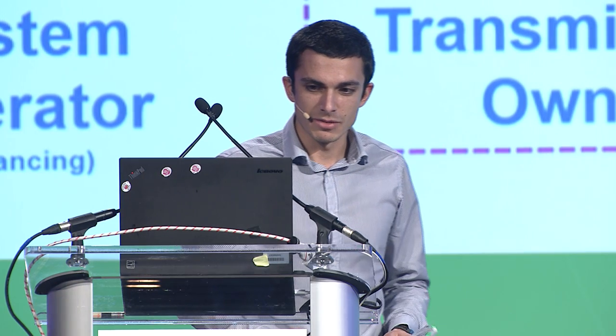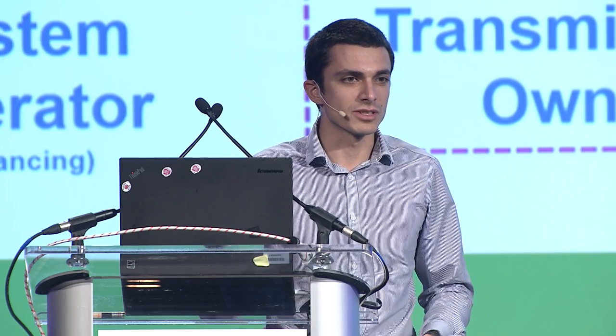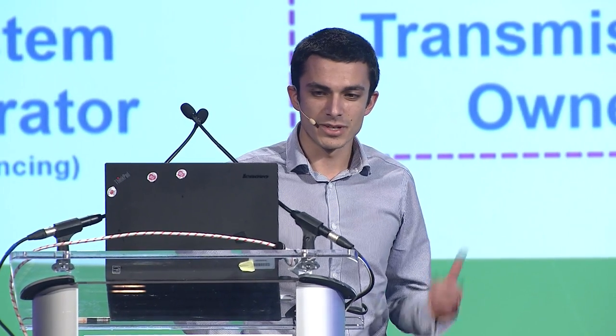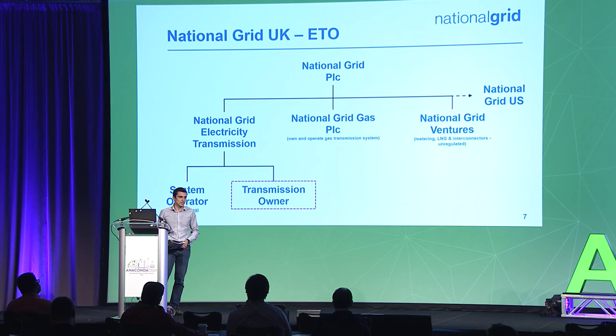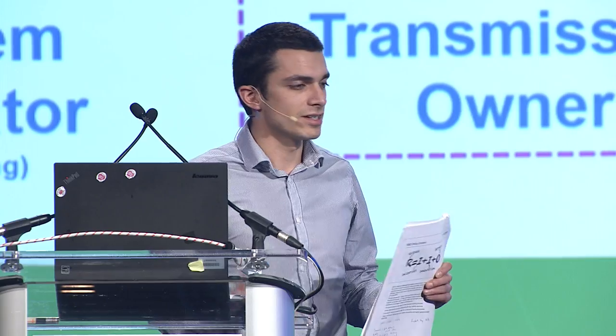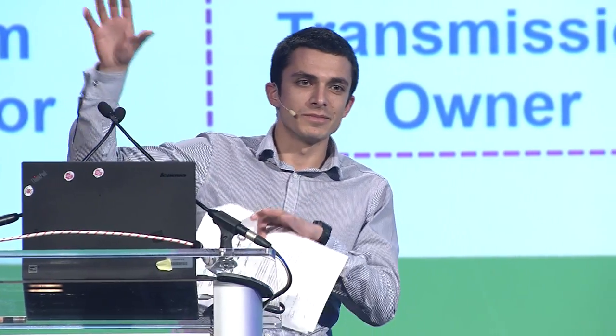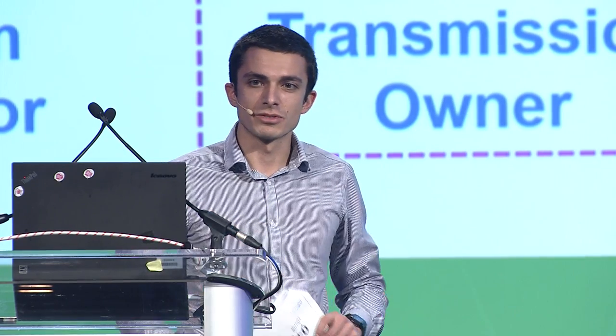In the UK, in England, we have this phenomenon called TV pickup — when a TV show finishes, everyone goes to make a cup of tea, open the fridge, flush the toilet, and there's a surge of electricity. The system operator has a team responsible for monitoring TV schedules and following plot lines on soap operas and large sporting events. Half-time in a football game is very important. They'll bring on pump storage stations — there's a large one in Wales with two lakes, and opening the gates generates electricity within seconds.